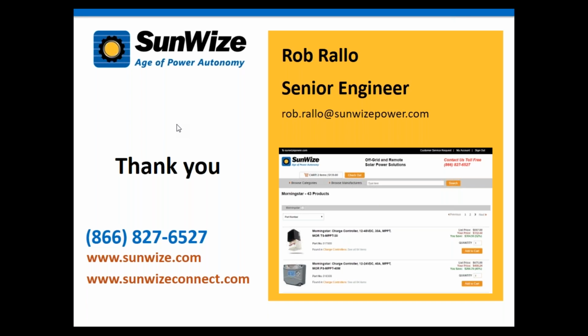And actually, maybe I'll address this in the next webinar in a little more detail. But what it does is it helps the performance in the sense that if your battery doesn't get to a full charge regularly, it'll help eliminate some of the sulfation. On a regular lead acid battery, whether it be valve regulated or flooded, if the batteries don't get a full state of charge, then sulfate crystals can build up on the plates, and they can become permanent if they sit there a long time. In a flooded battery, you can actually equalize the battery and stir up the electrolyte and knock those crystals off the plate to some extent.